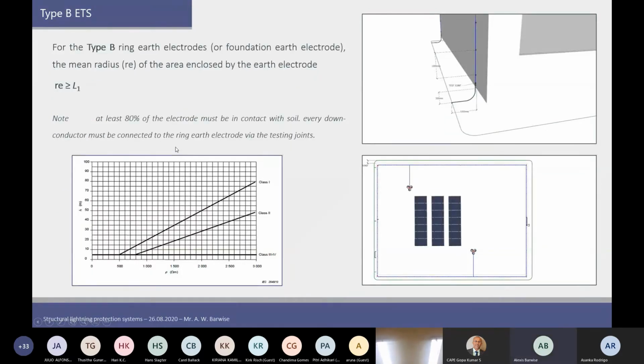For the type B system, here we can see it's a ring earth electrode, or an electrode around the entire building. Right there we can see it. There we use the mean radius. So we work out the mean radius of the square, and that value still has to be greater than the minimum length. And here we see the figure from the standard. It states that, as an example, for lightning protection level 1, if the soil resistivity is 1,000 ohm meters, we need to have a length of 20.